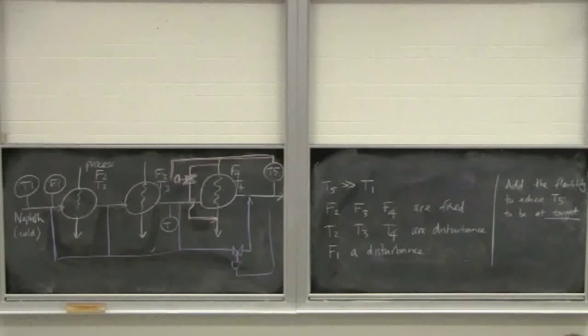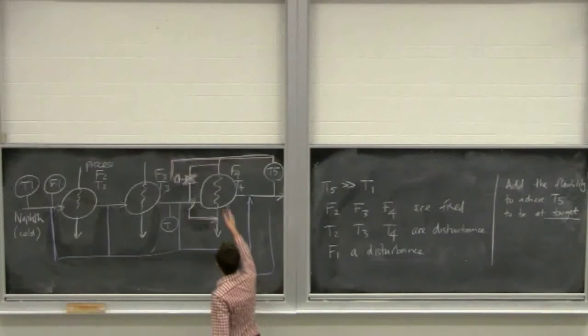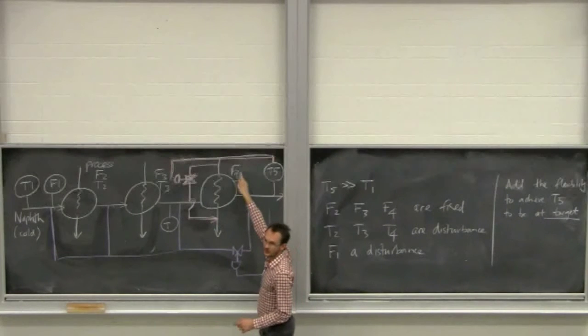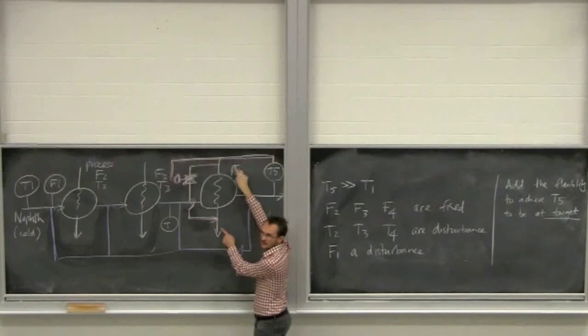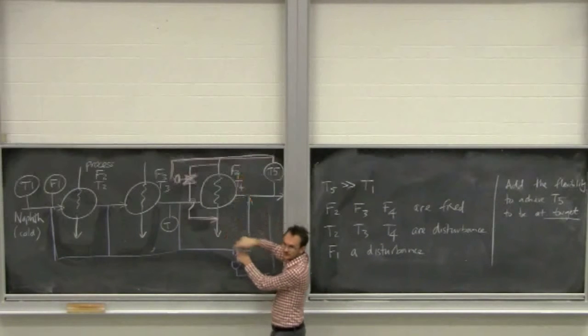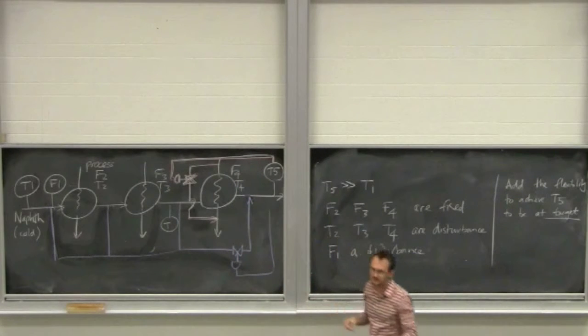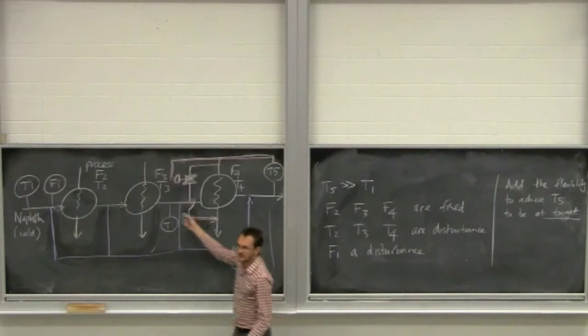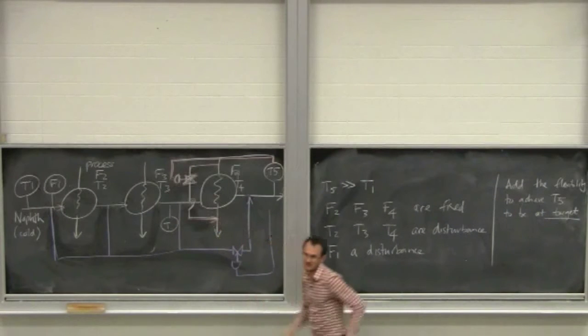Wouldn't the disturbance to your fixed flow in that sense be very minimal at all? Sorry, 4. Like, if you did have that bypass run, would that be a very minimal disturbance to the flow? It's not a disturbance to the flow at all. The F4 here is the same as the F4 there. It's a disturbance to the temperature. Well, we'd have disturbance to temperature in the standard setup anyway. Less so though.